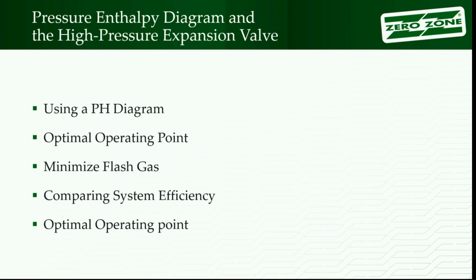So we're going to talk a little more now, in a little more detail. That was just the opening salvo on the pressure enthalpy diagram. We're going to talk about using a pressure enthalpy diagram. We'll talk about then the optimal operating point. What is the software picking and why is it picking that point? And then we'll look at flash gas minimization. Then we're going to compare some system efficiencies. I used the Bitzer software, ran some different discharge pressures for the same temperature, and we can see how that works. Then we'll tie that back to why we have the operating point that the software selected.